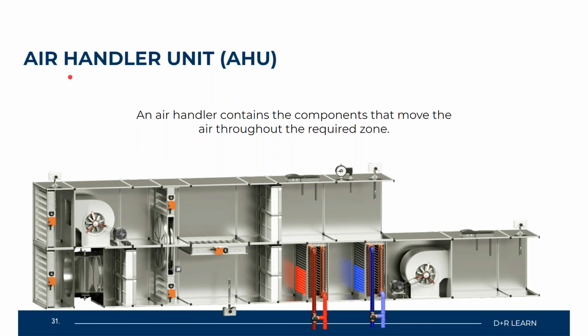What we have here is the AHU, or air handler system. For some of us that are HVAC technicians in class today, you may have heard this system called the AHU unit, but it is an AHU, or air handler unit system. And the air handler unit system is usually set inside a facility where you can have both your heating and cooling components of your HVAC system put together in one. So what your air handler system is utilized for is to draw in air and also supply air and exhaust air from your spaces within your facility.